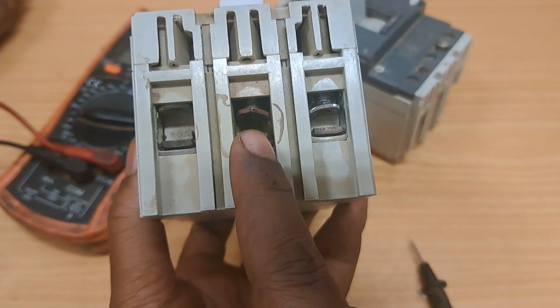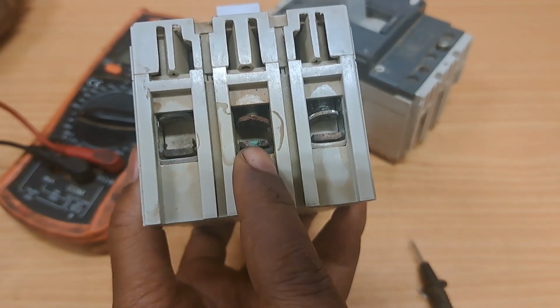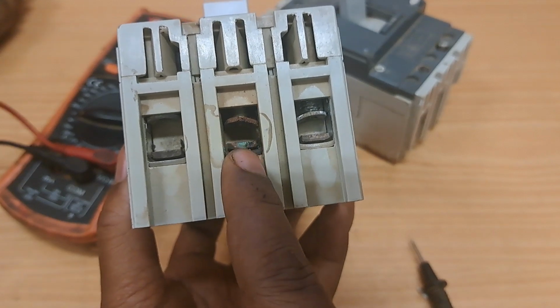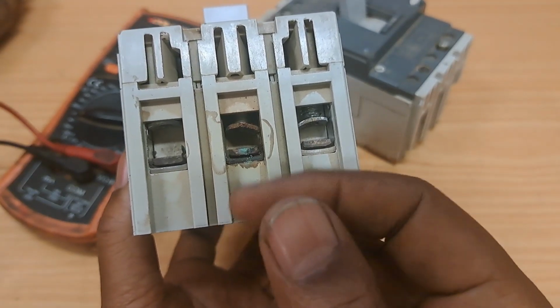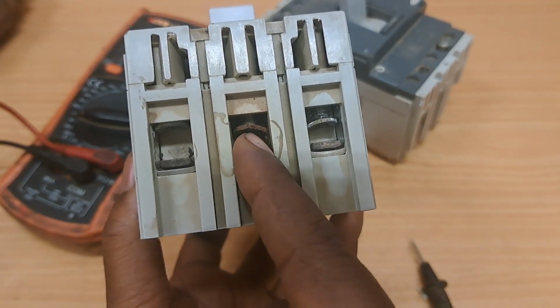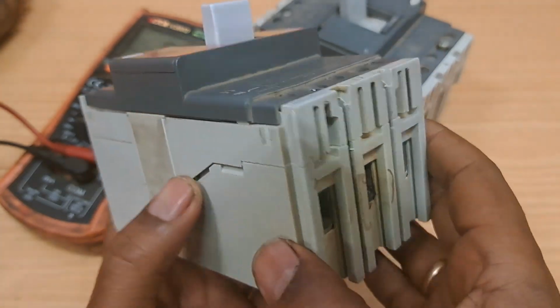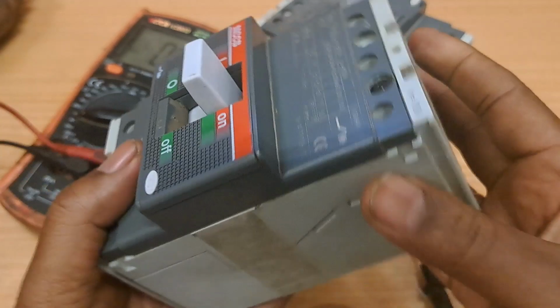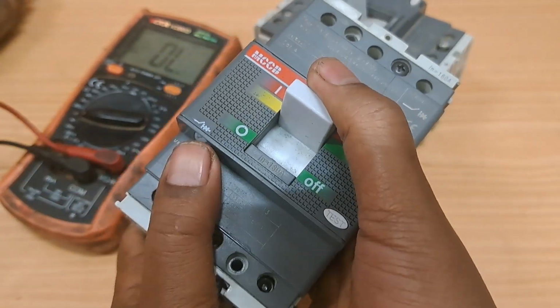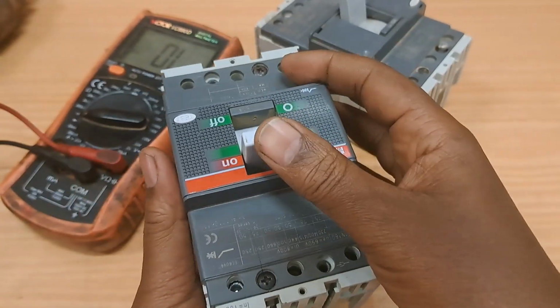You see, if there is excessive current like this in one of the phases due to a loose contact, that can cause excessive arcing, and it can cause excessive current flow, and that can be very damaging to the circuit breaker. So let's go ahead and see if it is latching to the off and on positions.